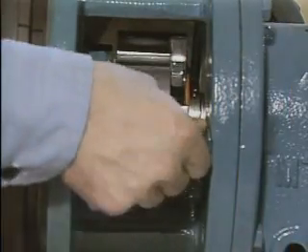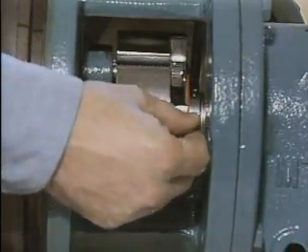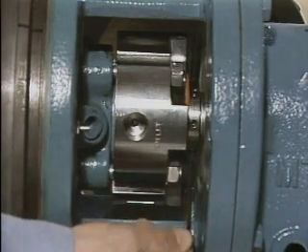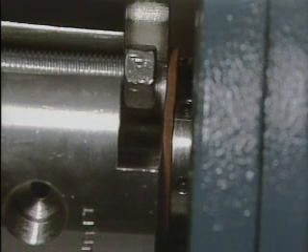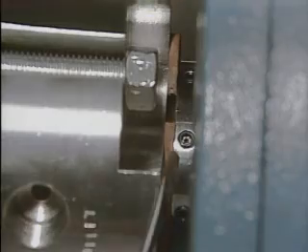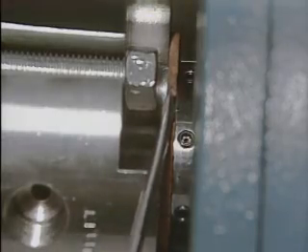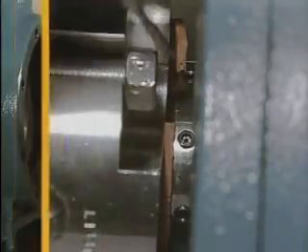Then the set screws on the collar are tightened. In this case, the collar and set screws hold the cartridge sleeve to the shaft. Most cartridge seals have some type of device, such as this rubber bushing, that holds the rotating element in place and keeps the proper amount of compression on the seal's springs until the seal is installed. The bushing must be removed before the seal is put into service.